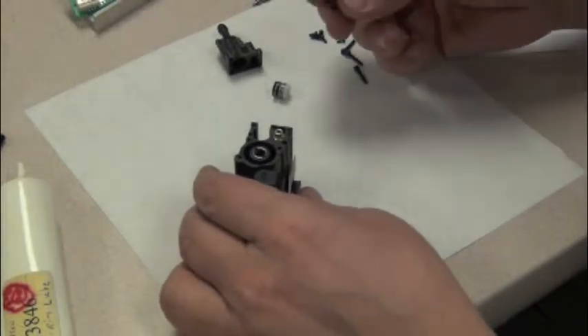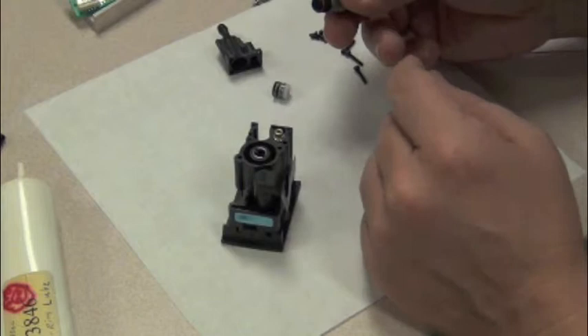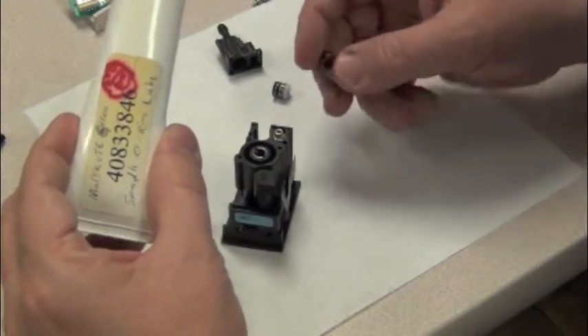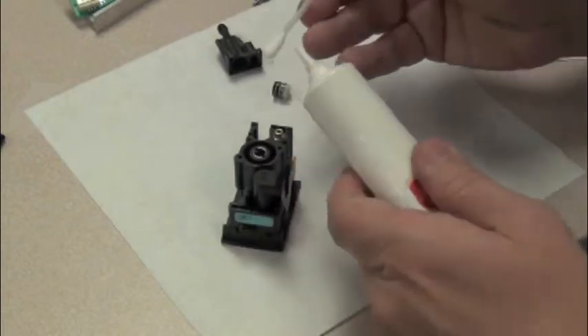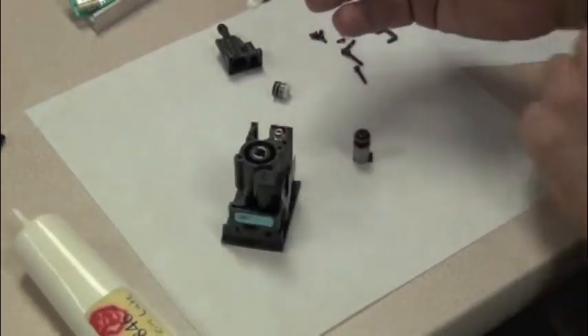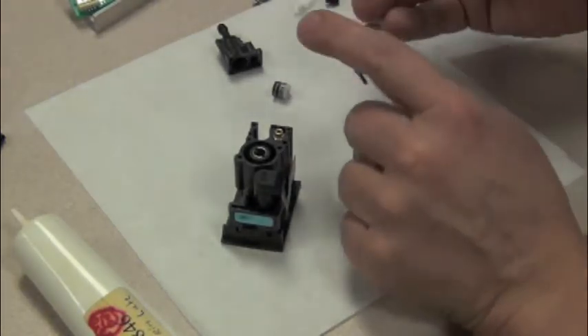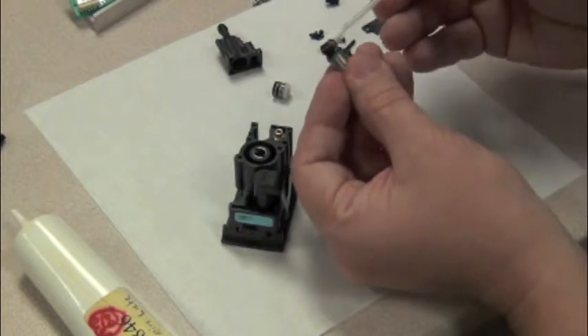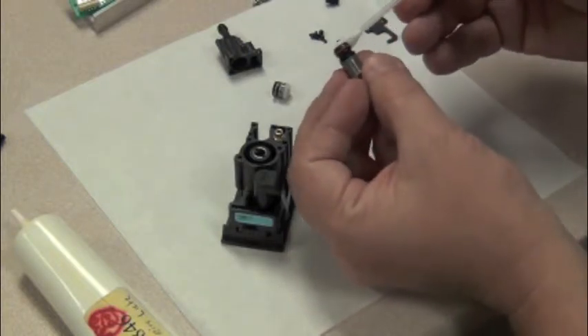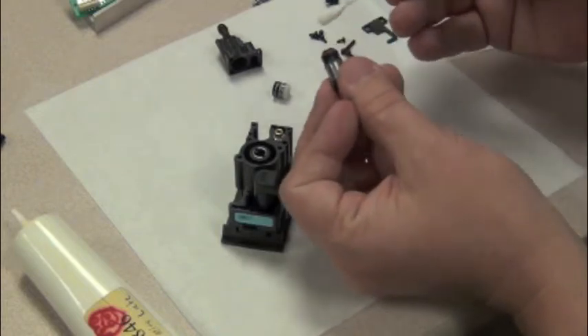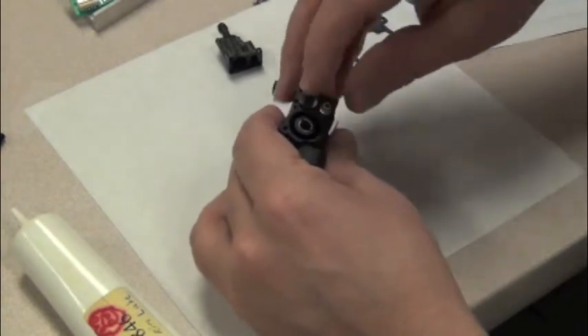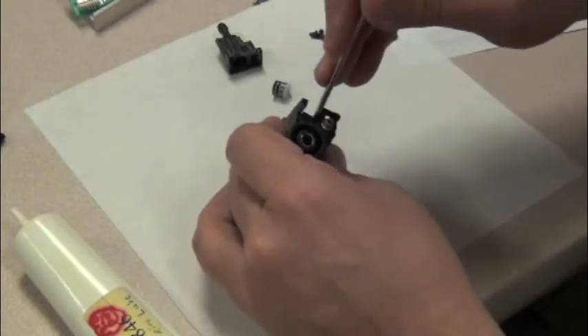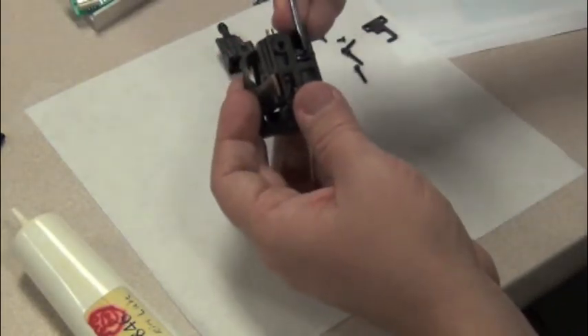Now we're going to grab our poppet valve, our vacuum valve. Because it's a new valve with new O-rings, we're going to have to use the moly coat G 4500 spindle O-ring lube. We don't want to put too much on, so we're going to grab an ESD swab. We're just going to put a little small dot, about two millimeters. Then we're going to wipe that on the ESD swab with a clean finger. We're going to grab the valve and wipe both the red and the green O-rings all the way around the valve with a nice thin coat. Next we take the valve and place it in the lower assembly. You want to make sure that you don't push on the actual black circuit board, but instead on the sides, the silver sides there. Take a look at the valve and make sure that it is square to the body.